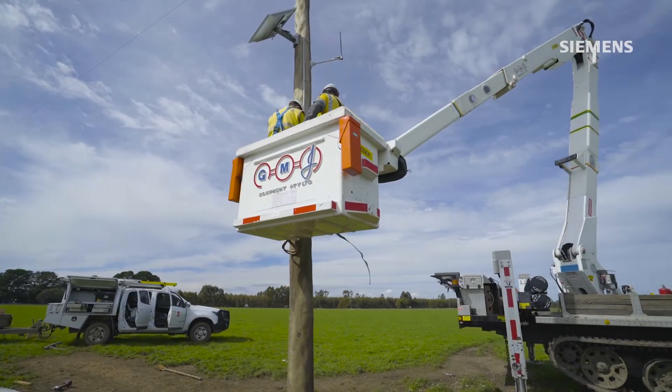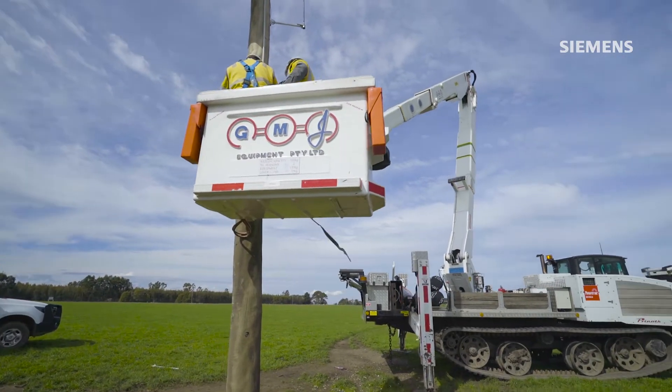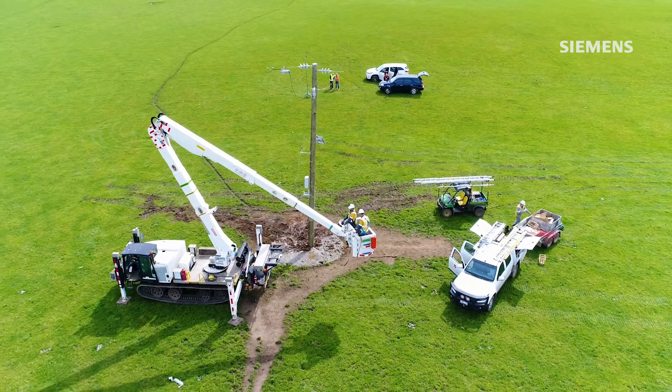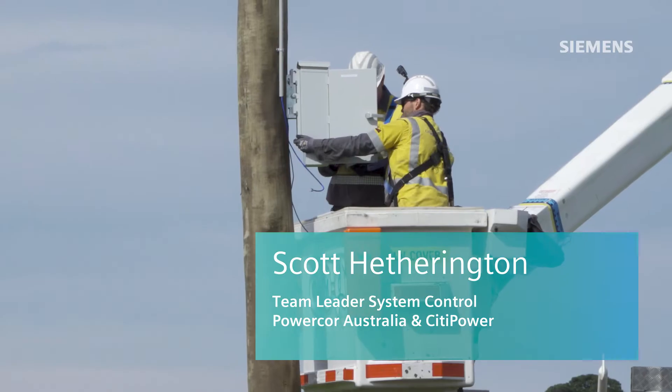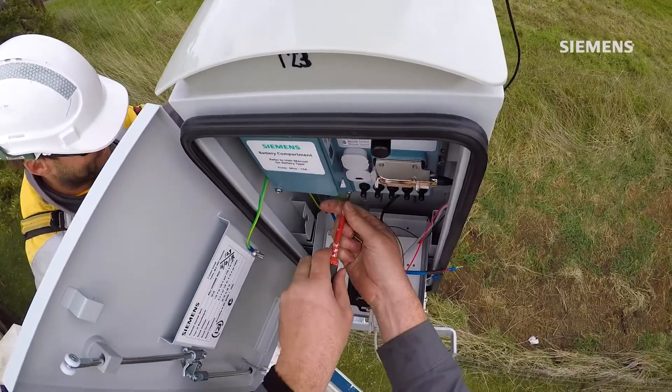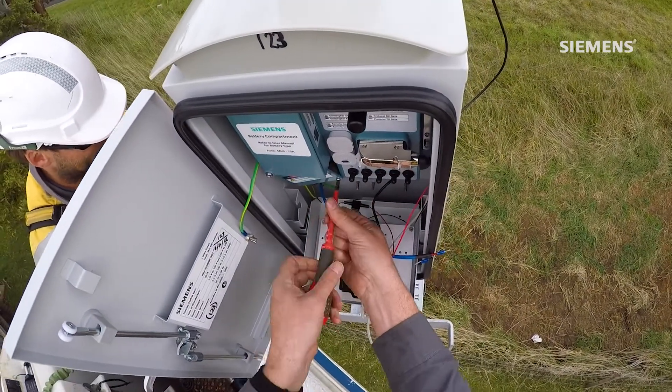Siemens were a big part of that. It's typically about a three-hour installation time, which is a lot more beneficial than the typical ACR installation of around eight hours on a total fire ban day. We now have the ability to remotely change the suppressions or requirements at the fuse savers, and using the computer system it can take us just 30 minutes to complete those suppressions.